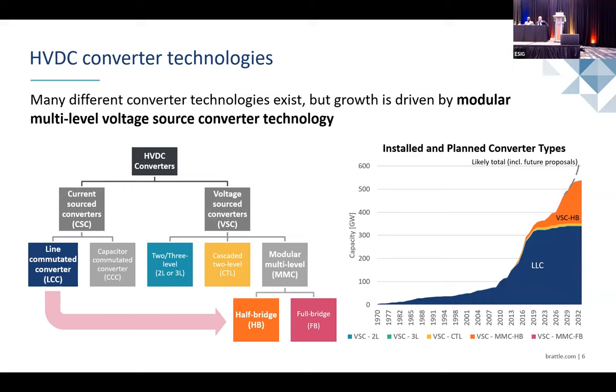In CCC converters, you also see a thyristor bridge, plus you also see a capacitor. The main purpose of adding this capacitor in this type of converter is to improve the functionalities, particularly when you are connecting line commutated converters to the grid. They do have some problems, especially when you connect to weak grids. We can overcome these problems with capacitor commutated converters.